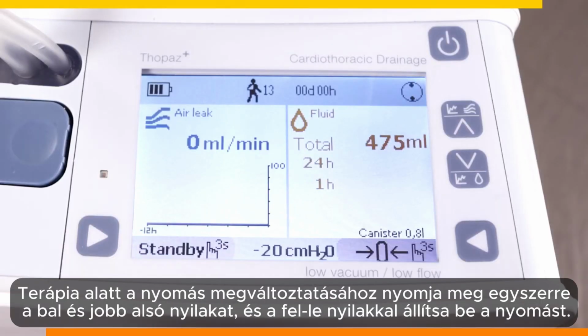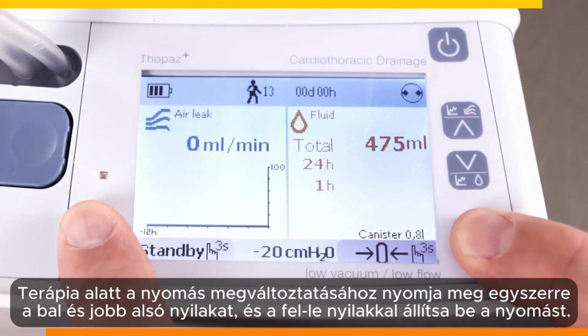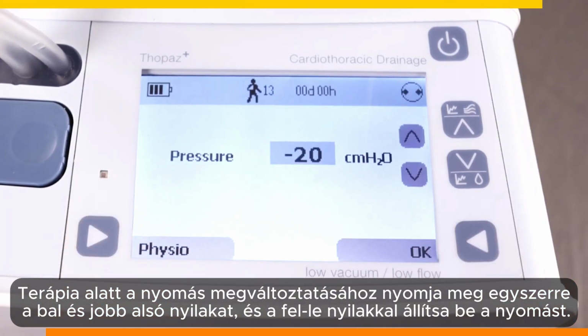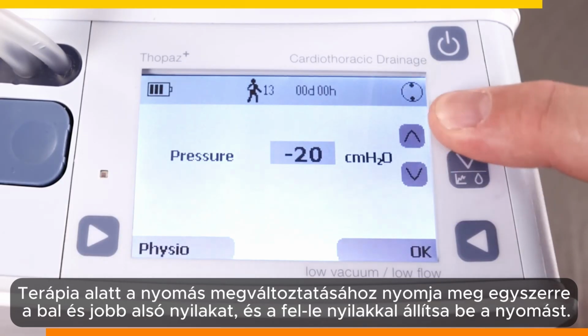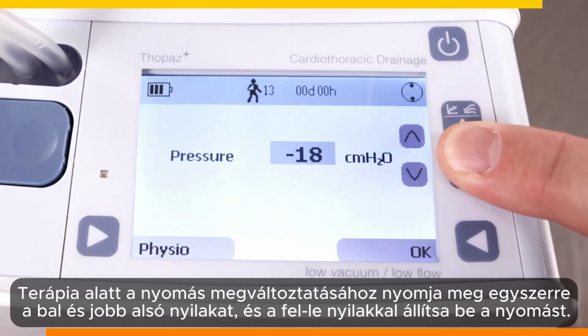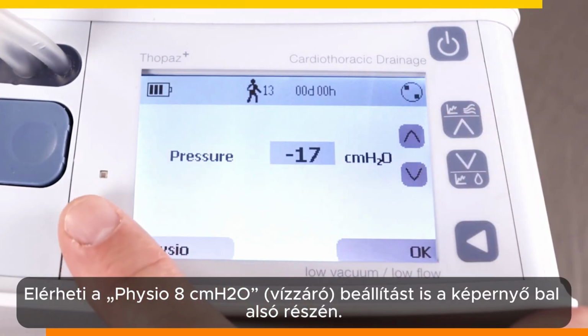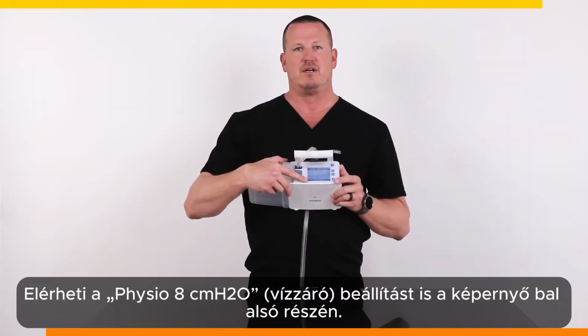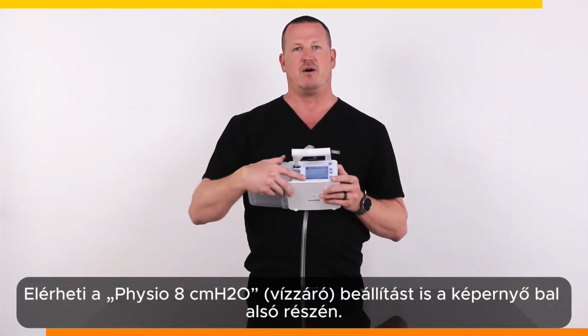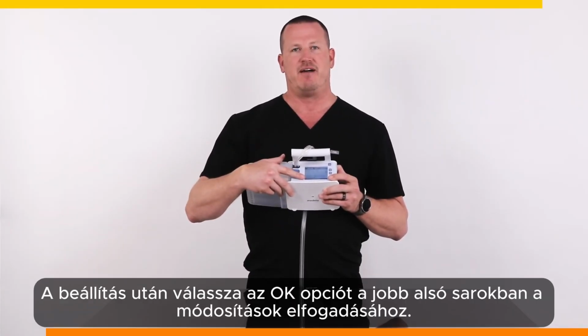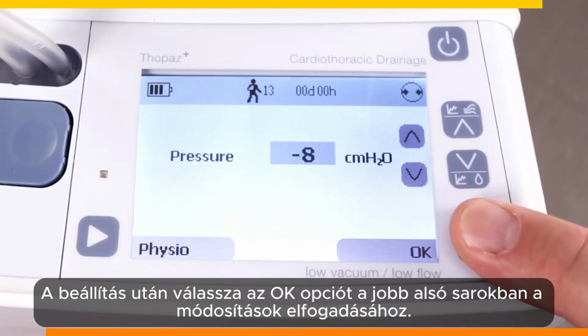To change the pressure mode during active therapy, press the bottom left and right arrows simultaneously and use the up or down arrows to adjust the pressure. You can also access physio mode, -8 centimeters of water, for the water seal setting on the bottom left of the screen. After making your adjustment, select the OK option on the bottom right to accept the changes.